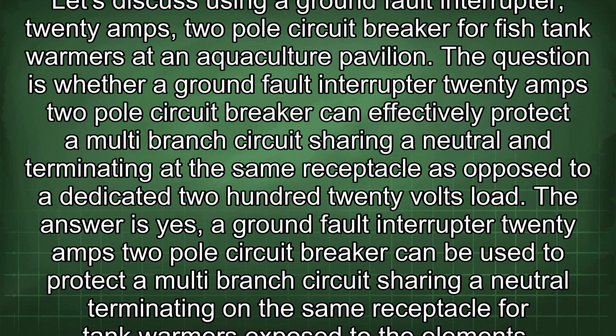The answer is yes. A ground fault interrupter 20 amps 2-pole circuit breaker can be used to protect a multi-branch circuit sharing a neutral terminating on the same receptacle for tank warmers exposed to the elements.